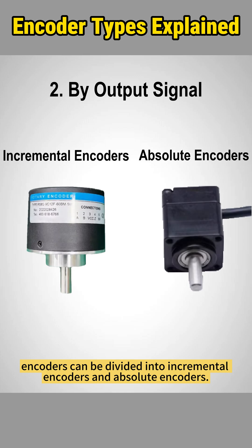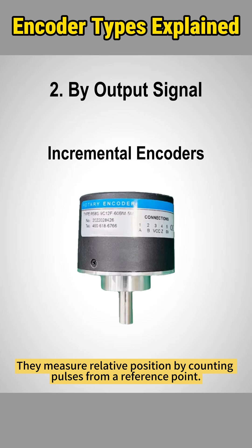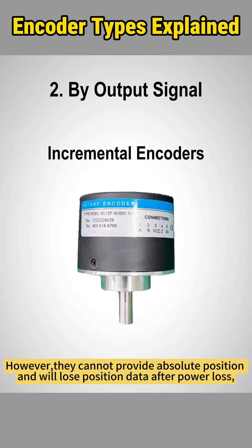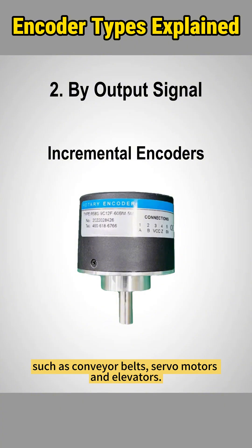By output signals, encoders can be divided into incremental encoders and absolute encoders. Incremental encoders generate pulse signals to track angular or linear movement. They measure relative position by counting pulses from a reference point. Their advantages lie in their simple structure and cost-effectiveness. However, they cannot provide absolute position and will lose position data after power loss, requiring homing upon restart. They are widely used in position control and speed monitoring applications such as conveyor belts, servo motors, and elevators.